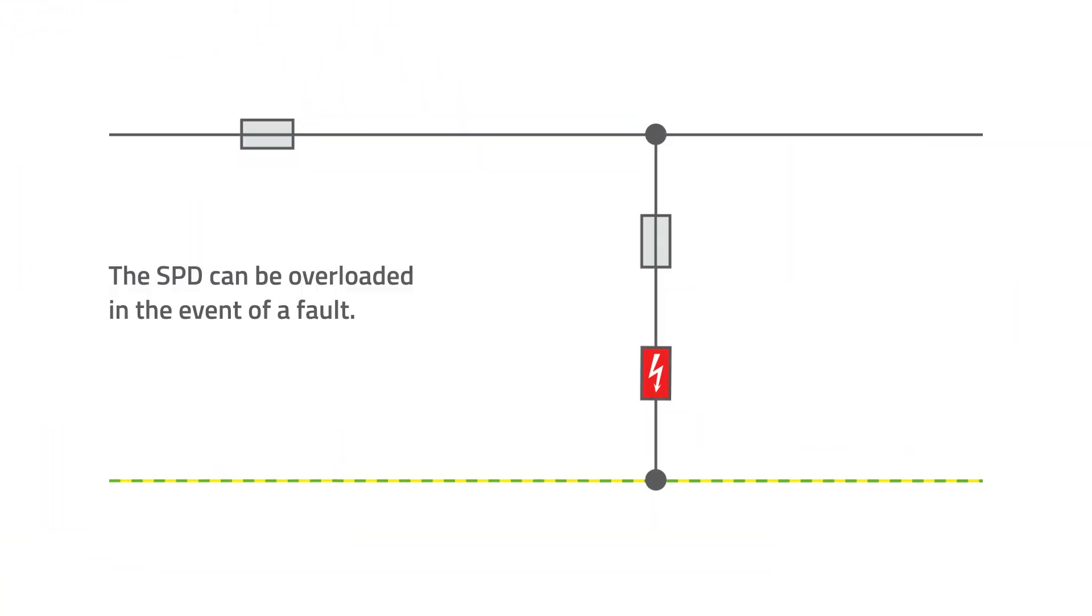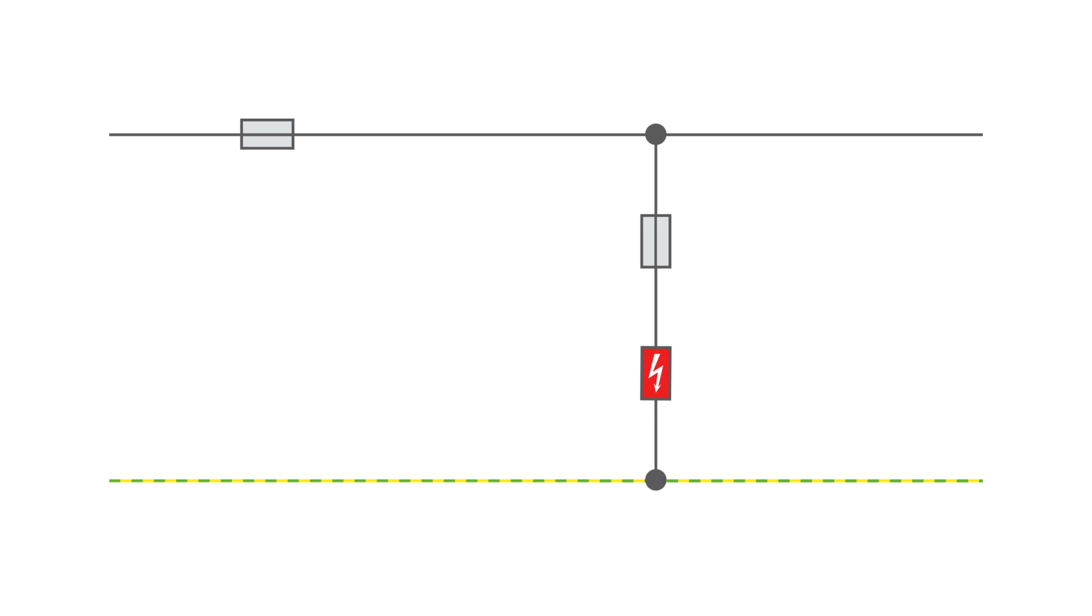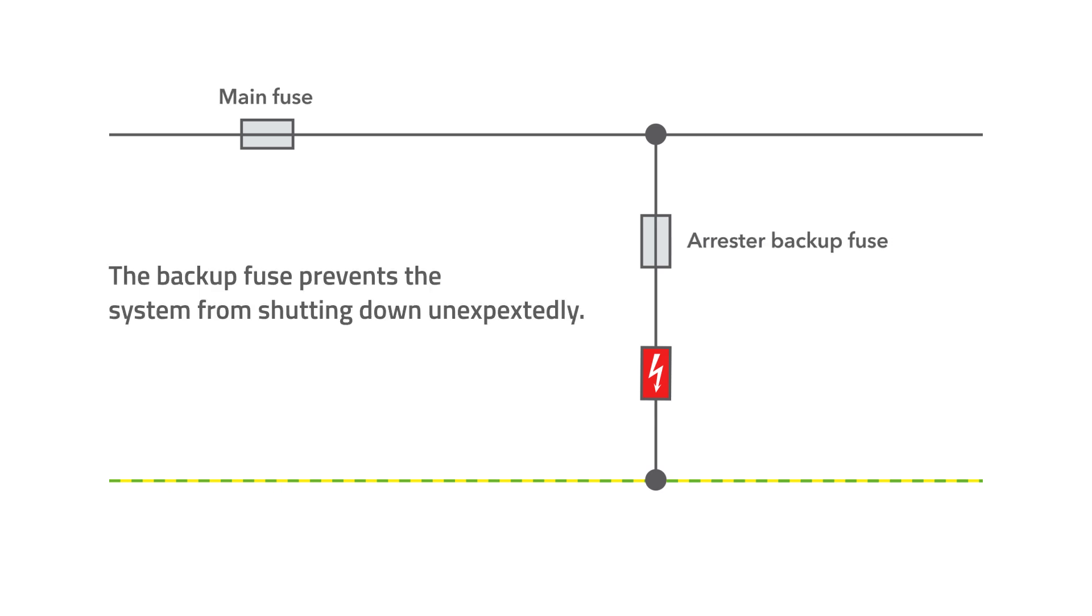But why use a backup fuse at all? Because the surge protective device, or SPD, can be overloaded in the event of a fault. The arrestor backup fuse, which trips before the main fuse, prevents the entire system from shutting down unexpectedly.